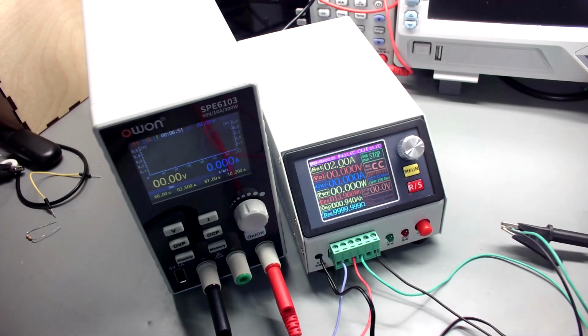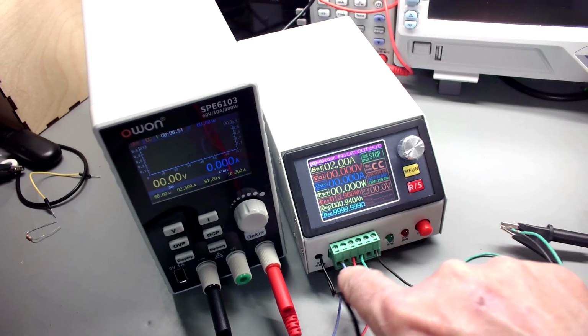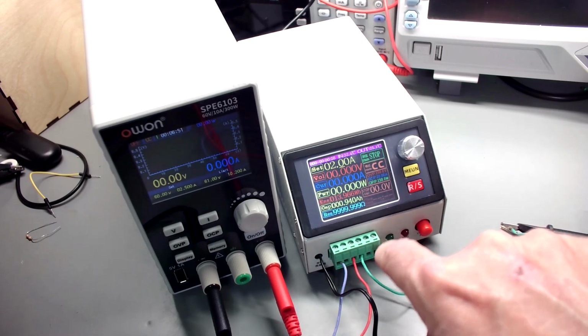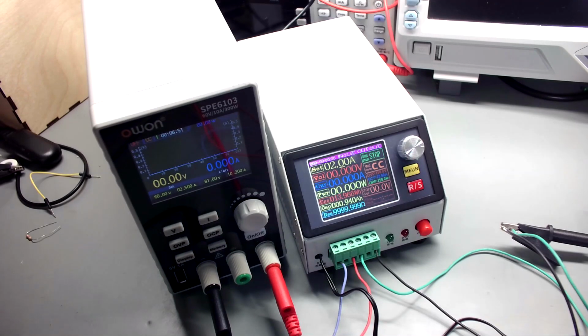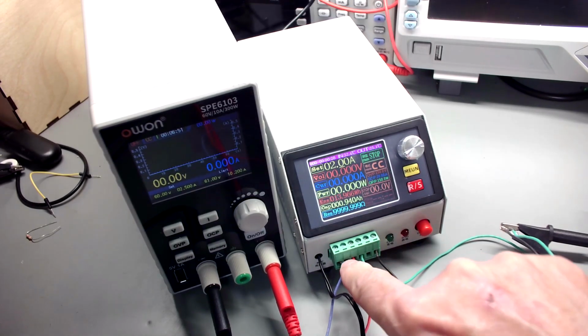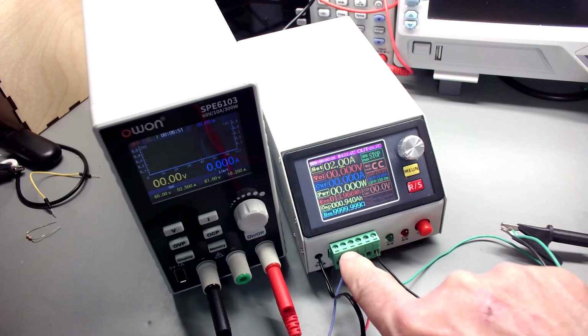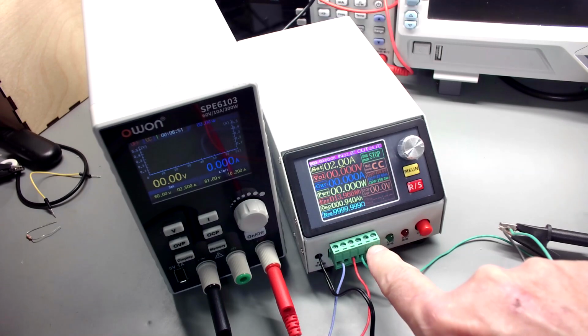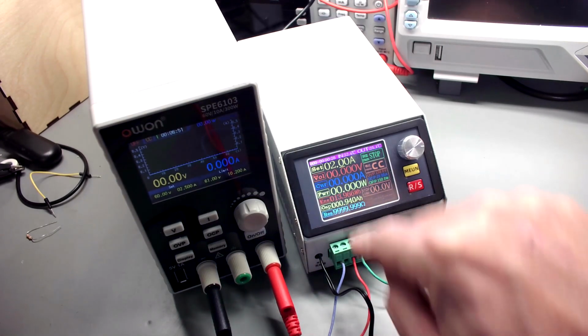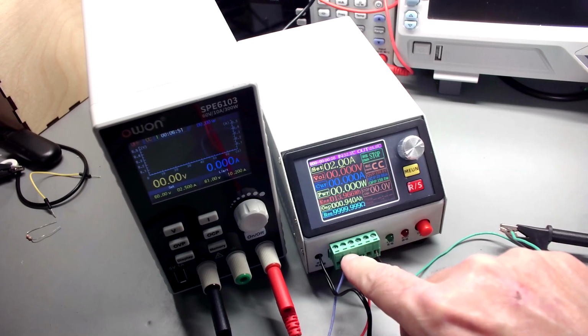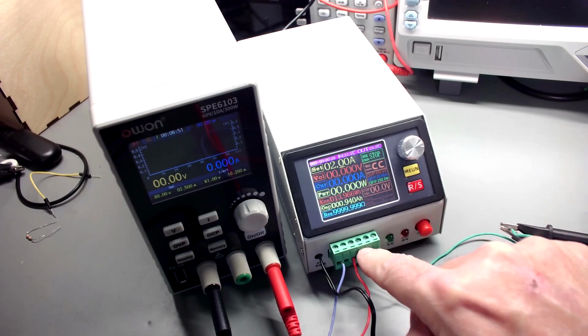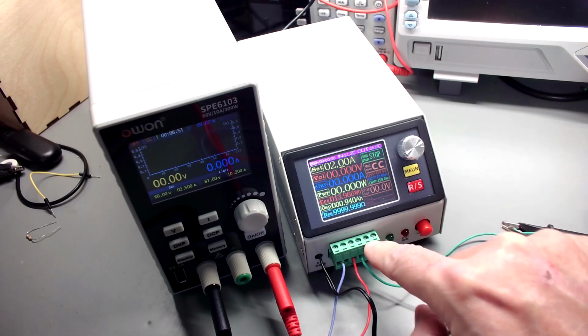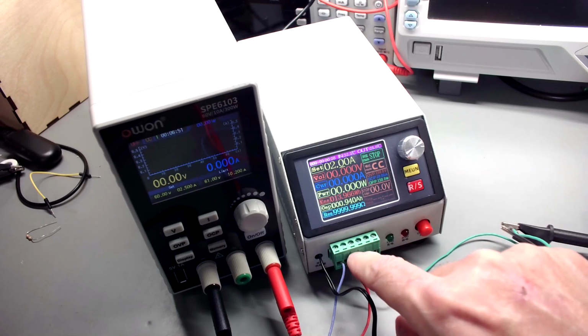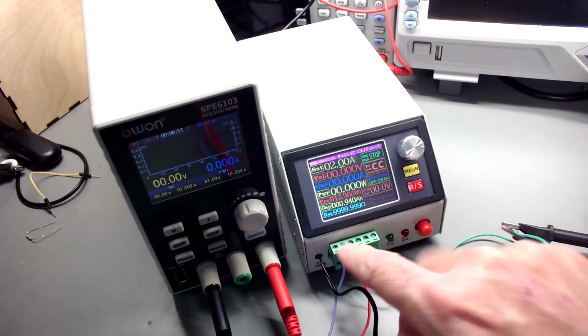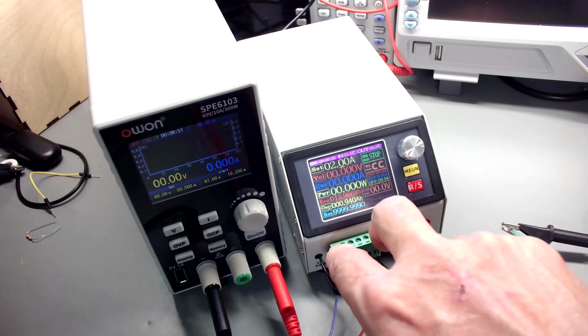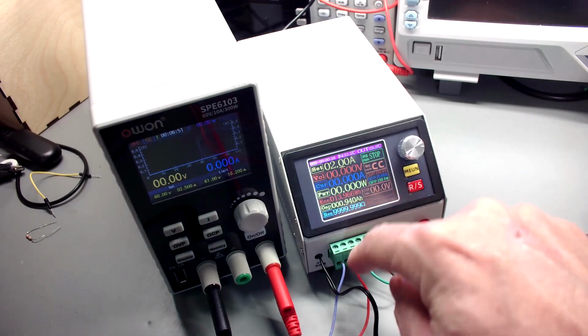Kind of a nice feature: you could just jumper these together to alleviate that. I think what they're getting at is there's two currents - current positive is the first and second post, current negative is the last post and the next one to it, and your voltage is in the middle. So it makes sense that if we jumpered the voltage to the center post, and the negative voltage to the second to last post, putting a jumper here and here would mean you only hook up once. So if you want to do single wire or two wire measurements, just put a jumper there and you're good to go.